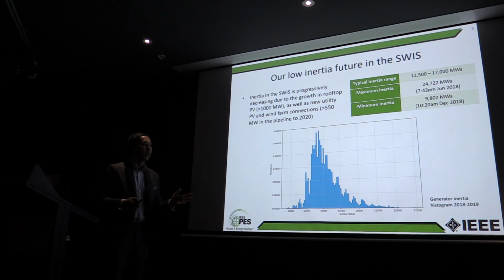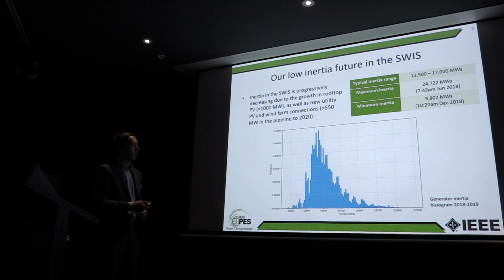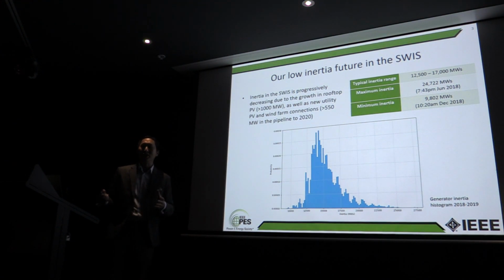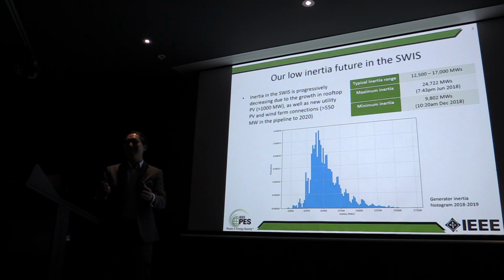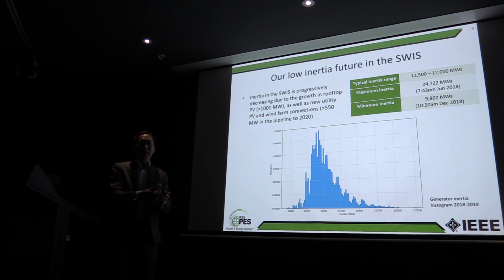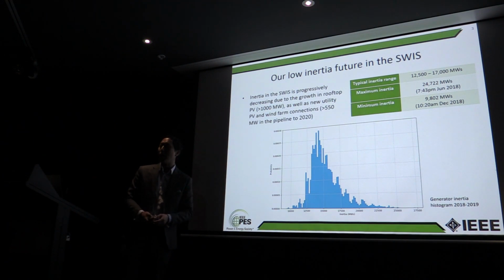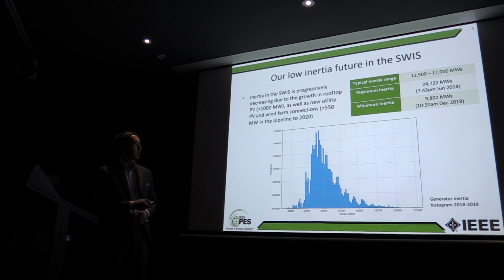So these are the last 2 years of inertia as a histogram. And you can see it's not symmetrical. So most often it's in this 12,500 to 17,000 region. Sometimes it's large, and sometimes it's quite small. And what you also notice is that it's lumpy. This is because inertia occurs in chunks. So we put on a generator and you get 500 megawatt seconds. We don't get this nice smooth curve of inertia along the system. That's why you end up with these lumpy chunks there.